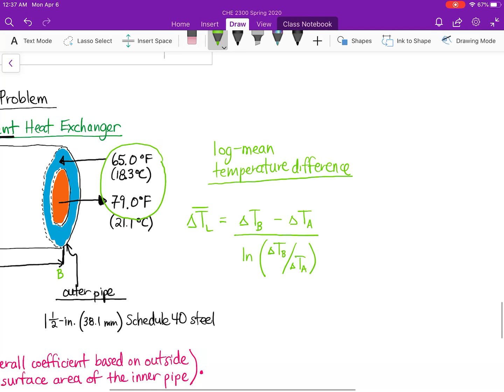For this particular example, my log mean temperature difference is going to be (141 minus 75) minus (79 minus 65), divided by the natural log of (141 minus 75) divided by (79 minus 65). This results in a log mean temperature difference of 33.5 degrees Fahrenheit for this heat exchanger.